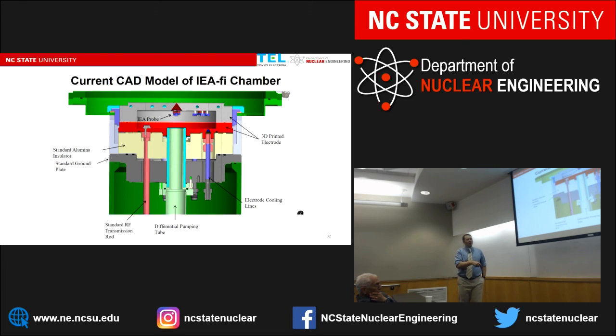chamber, we need to provide differential pumping. As I mentioned, if we don't pump it, then the pressure in between the grids can build up too high and we can get light up, whether it's due to Paschen's curve or even secondary electron emission, as you'll see in the next couple of slides. And so we have this differential pumping tube that we put through the center, which is typically where the lift pin mechanism to take your silicon wafer off would be. But the tube also allowed us to pull our wires out to take our RFEA measurement.